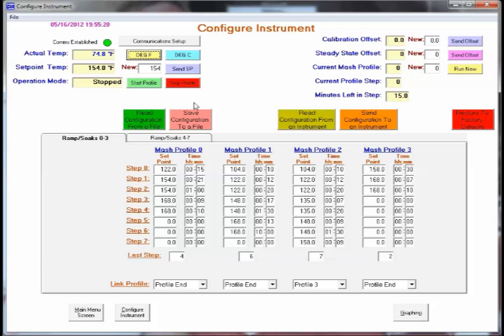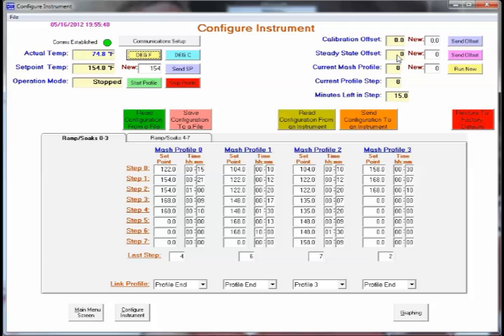Other parameters that can be set are calibration offset. If you have another instrument and you just want them to read exactly the same, you can enter a different variable like plus point one degrees or minus point one degrees for example. And then send the offset.